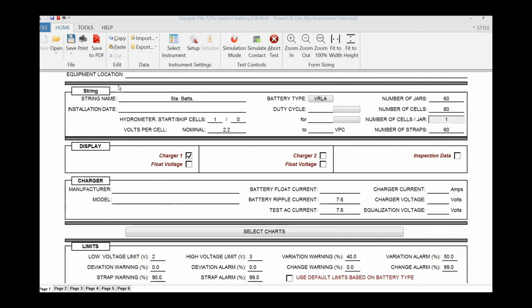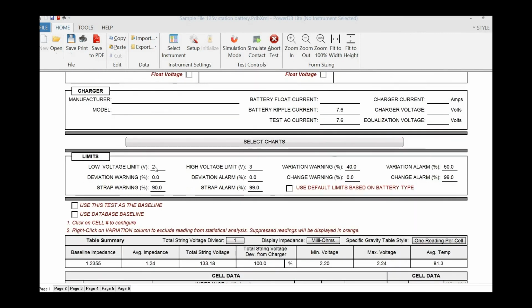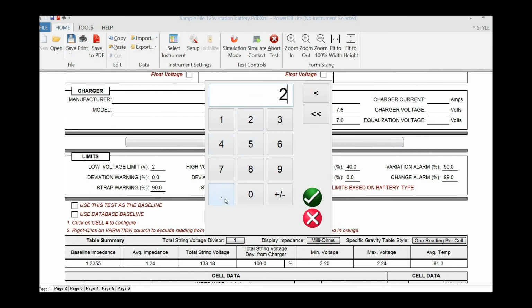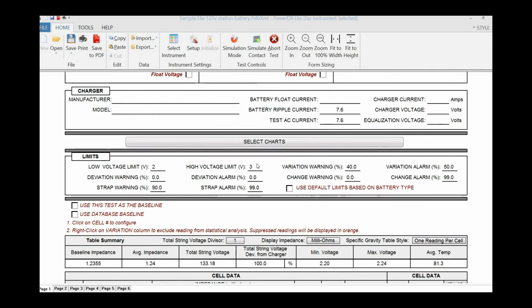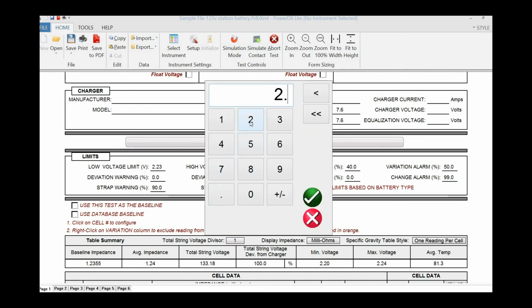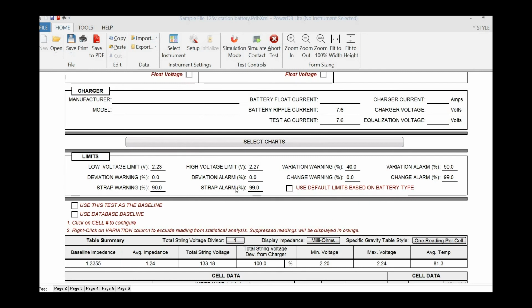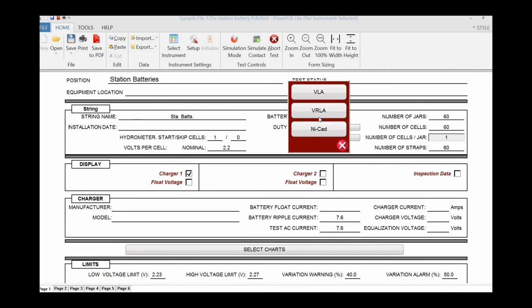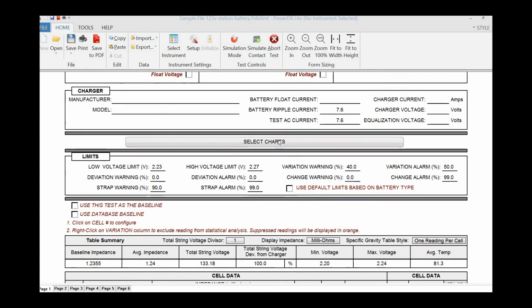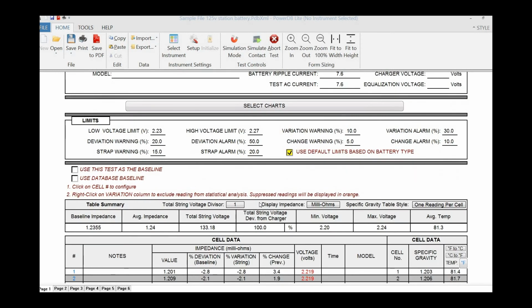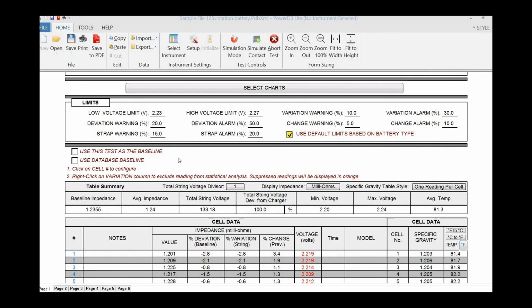To set the limits, scroll down to the Limits section of the report. If you know the limits you want to use, simply click on the desired field and then enter the desired value. If you do not know what limits to set, then scroll up to the string section of the report. Now select the battery type field and select the battery type. Now scroll back down to the limits section of the report and select Use Default Limits based on battery type. All the limits will now auto-populate except for the voltage limits. These you still need to set. Consult the battery datasheet or installation guide for these values. All these limits will now be used for all the following tests of this string.